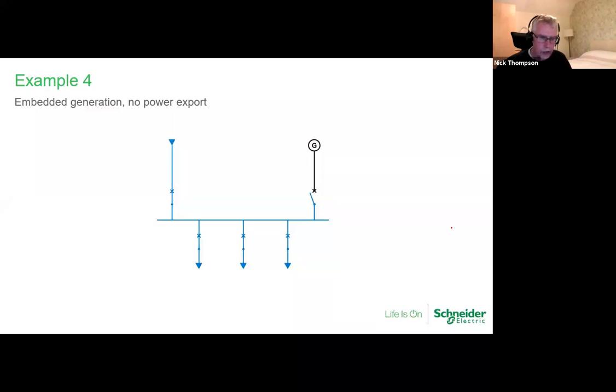So there's literally not those kind of arrangements that you can do. So there's going to be various different ways of achieving this. One of them is by a simple key exchange scheme, like the Castell type key exchange, where you would have an AP that would be authorized to do the tripping of the incoming circuit breaker, removing the key which will have become available when the circuit breaker has been tripped.